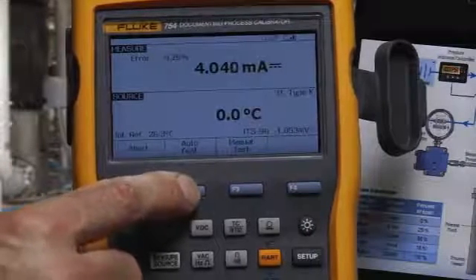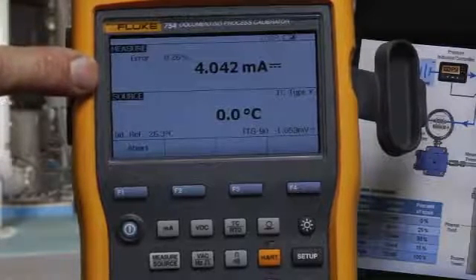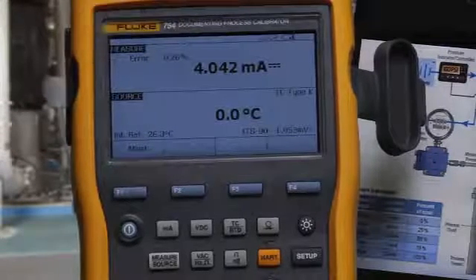Select auto test. The calibrator will apply the 0% temperature input, measure for 4 milliamps and calculate for error percent of span.